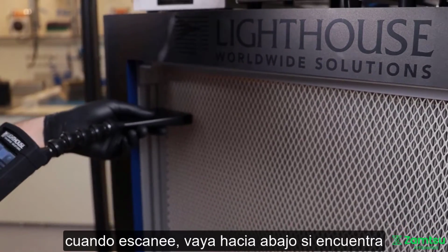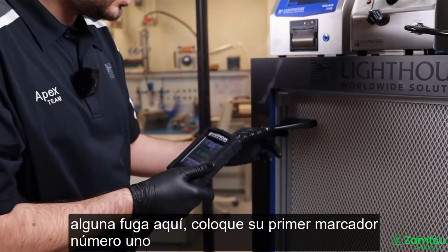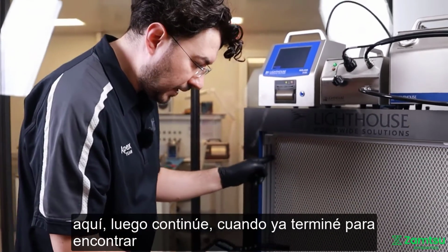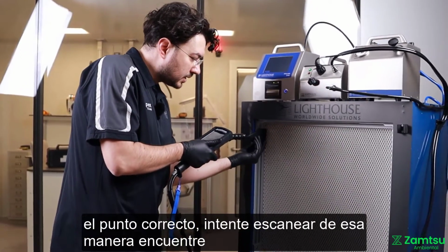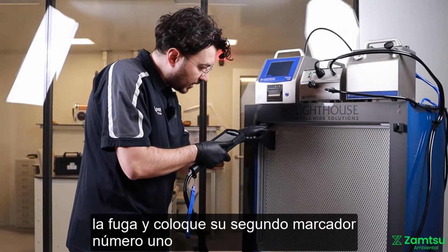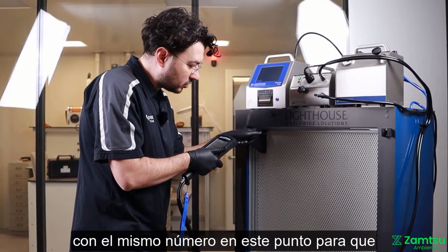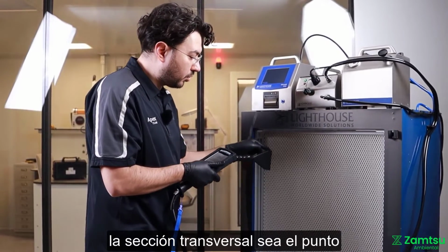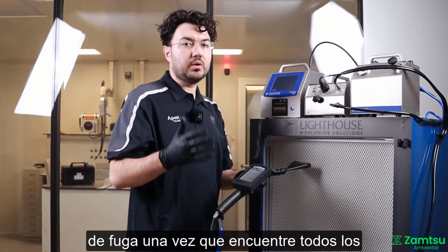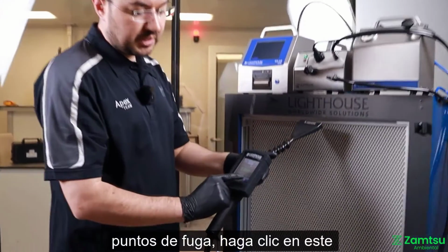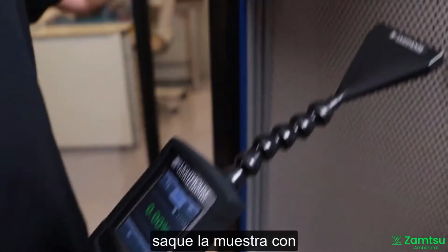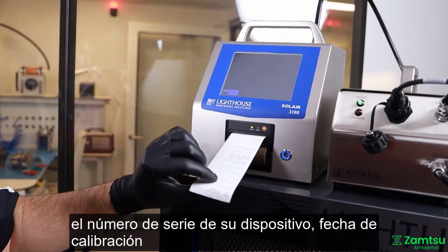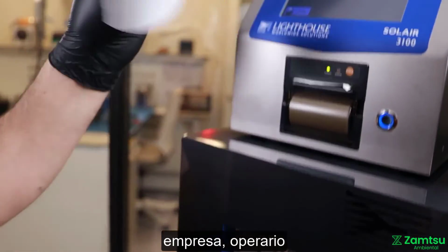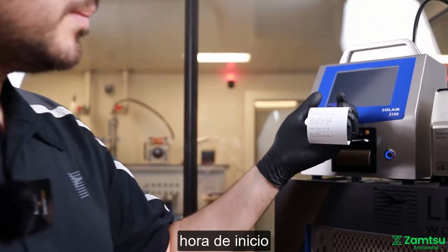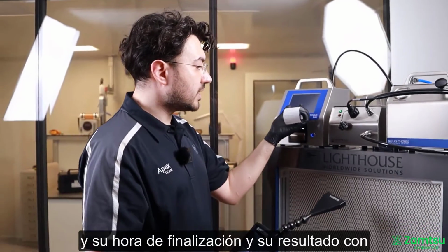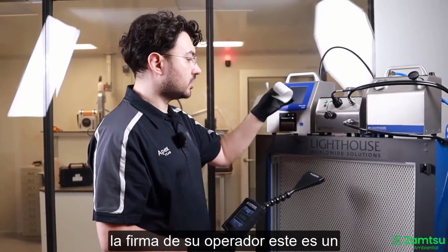In general, when you scan, go down below. If you find any leakage here, put marker number 1 here, move on. Once you're done, to find the right point, try to scan that way, find the leakage, and put your second marker with the same number at this point, so the cross section will be the point of leakage. Once you find all the leakage points, click on this printer mode, take out the sample with the serial number of your device, calibration due date, company, filter, aerosol that you are using, start time, leak alarm level, leak size, your upstream challenge, and your end time, and your result with the signature of your operator.